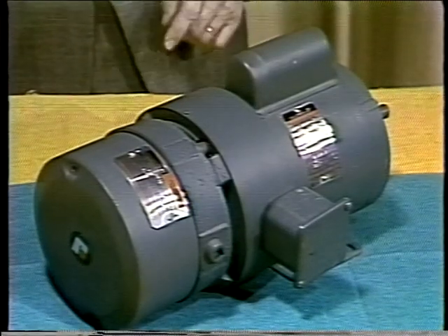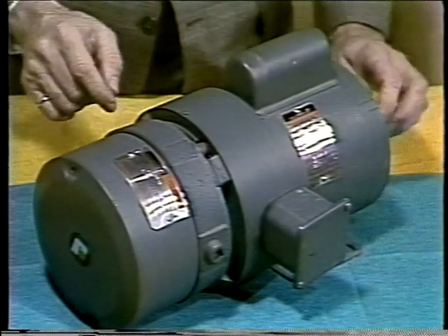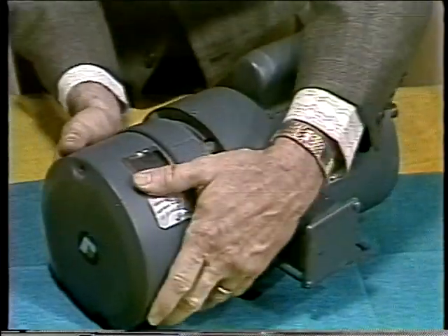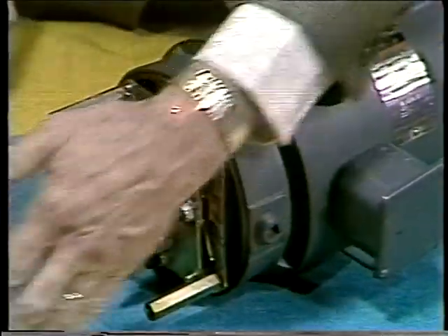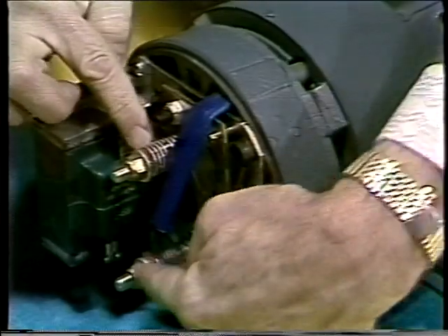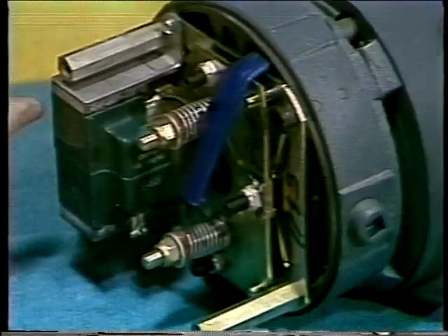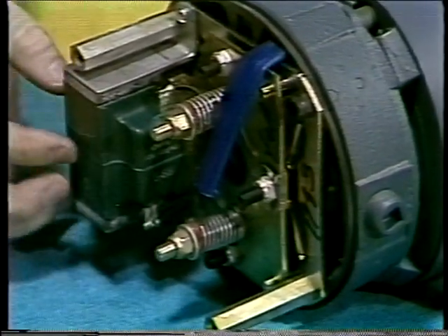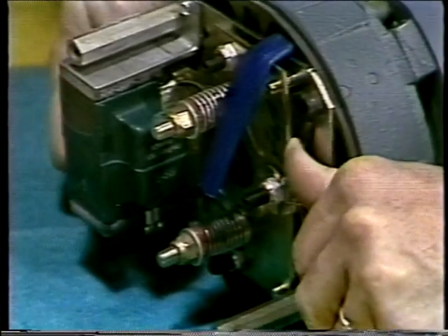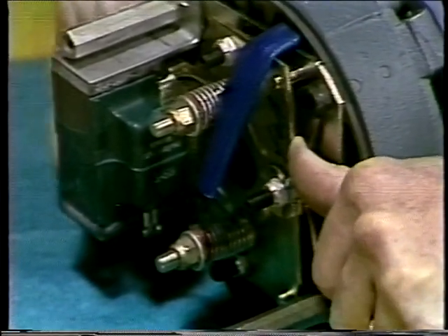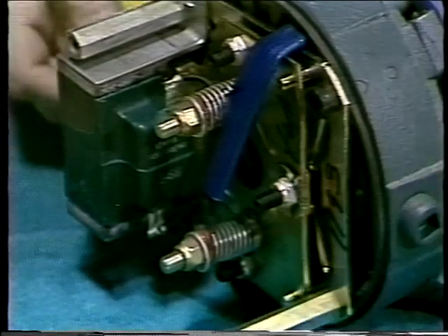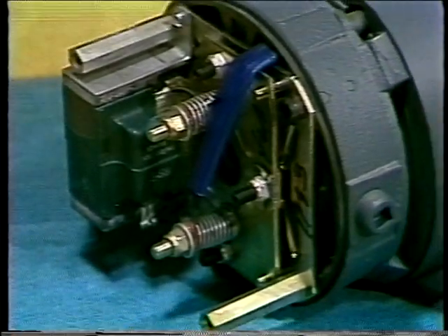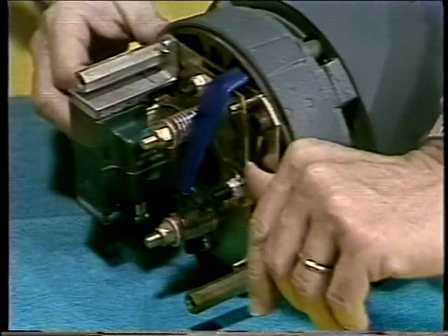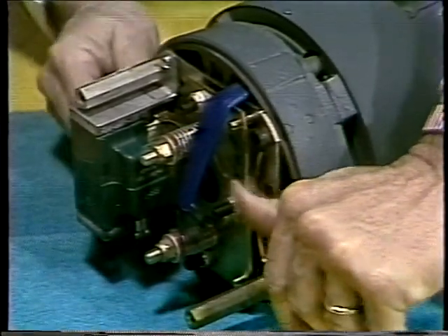Electromagnetic brakes are most frequently used on applications like electric motors. But in most cases, these are spring set. So we use an electrical magnet here to release the brake and a spring to apply the actuating force. This type brake is also used as a safety brake since the spring automatically applies the brake if there's a power failure. Electromagnets will be explained later in the tape.